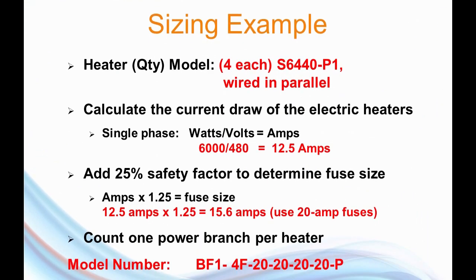Here's the first example. We're going to be wiring four of this S6440-P1 heater model — a 6,000-watt, 480-volt, single-phase heater. Calculating its current draw: a 6,000-watt, 480-volt heater draws 12.5 amps. Add a 25% safety factor, that's 15.6 amps. The appropriate fuse size is the next size up, which is a 20-amp fuse. The model number is: branch fuse, single phase, dash four branches, fuses, and then 20 for the fuse sizes. The P means the four branches are to be wired in parallel. That's our model number.